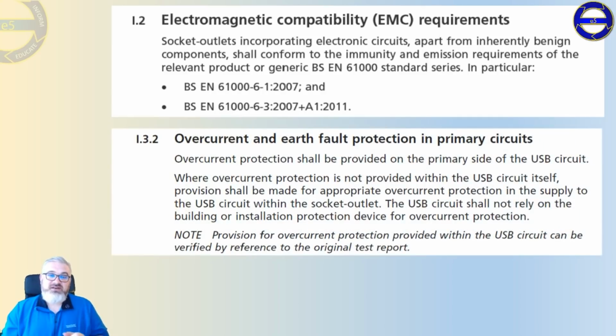Here's an interesting part of the standard, section I.3.2. It states overcurrent protection shall be provided on the primary side of the USB circuit. Where overcurrent protection is not provided within the USB circuit itself, provision should be made for appropriate overcurrent protection in the supply to the USB circuit within the socket outlet. So there must be overcurrent protection for the rectifier part of the circuit, coming from the mains, that short part internally. But it then says the USB circuit shall not rely on the building or installation protective device. So if I'm putting these on a BS 60898 Type B 32 amp circuit or a ring, we can't rely on that - there's got to be something inside the device itself.